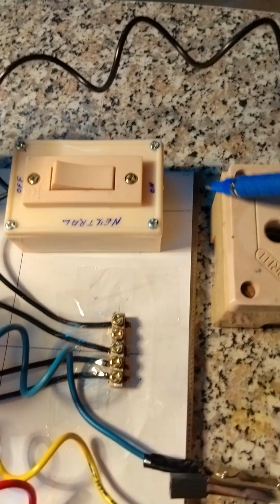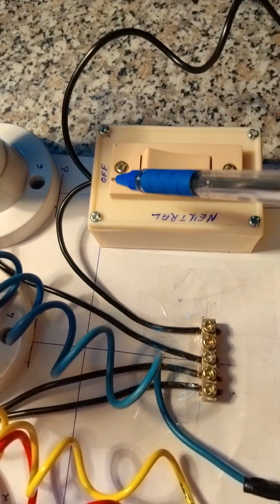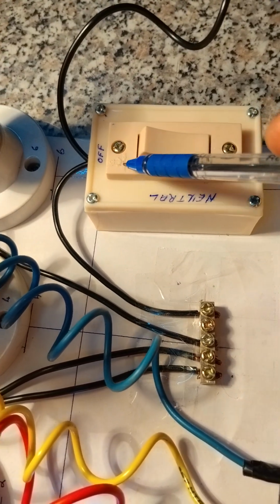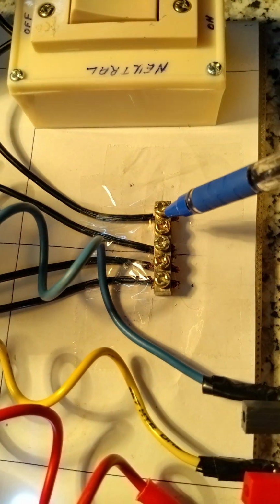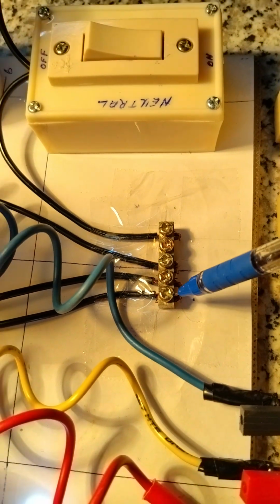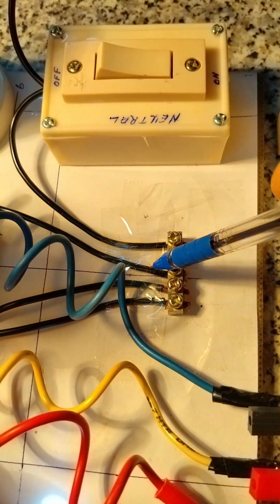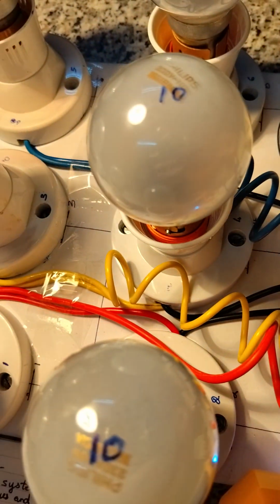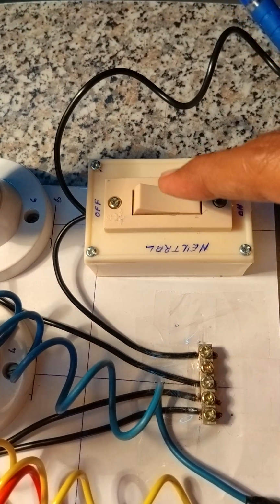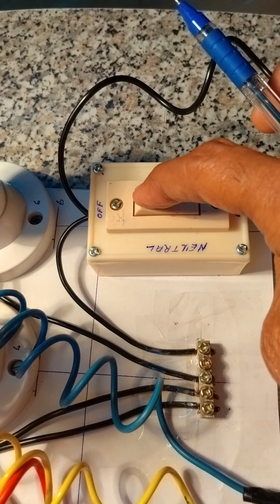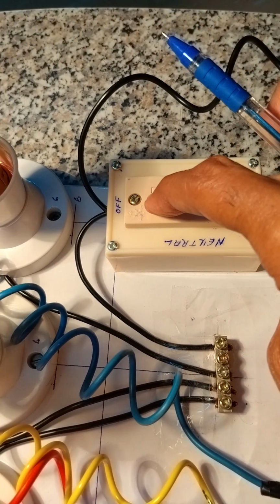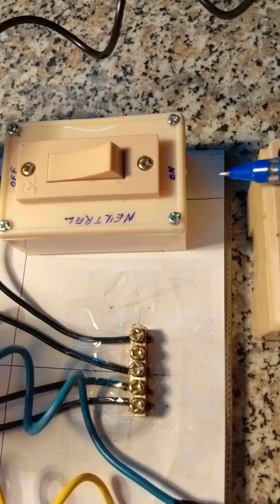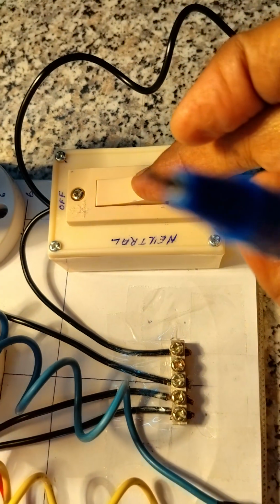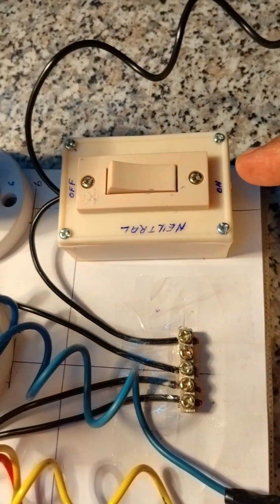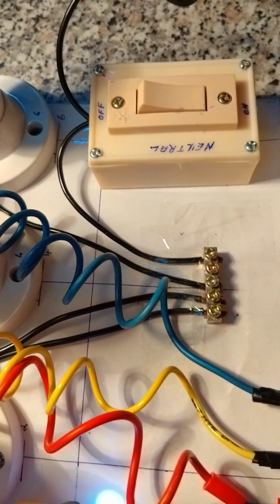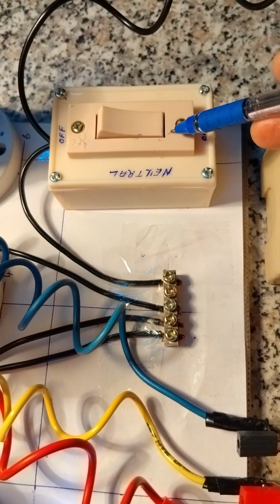This switch is for neutral. It comes into the switch and goes out and is connected to the star point, which is common for all the three phases. So I can disconnect and connect the neutral. This is connected and this is disconnect, off and on. Now it is off, now it is on. The purpose you will understand shortly.